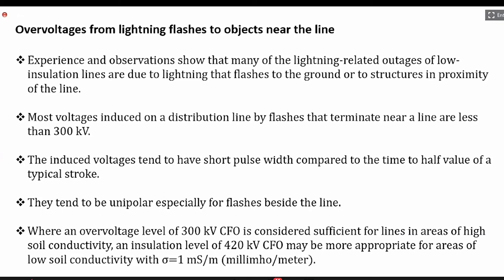And these lightning flashes induce voltages in the distribution line of concern. And most voltages induced on a distribution line by flashes that terminate near the distribution line are less than 300 kV. So can you remember, in the calculation also we came across a figure like 330 kV.